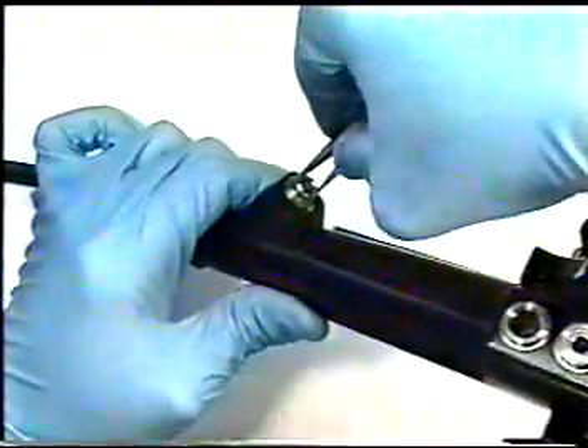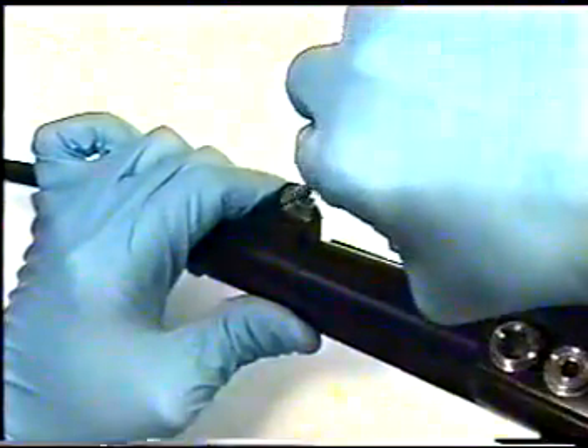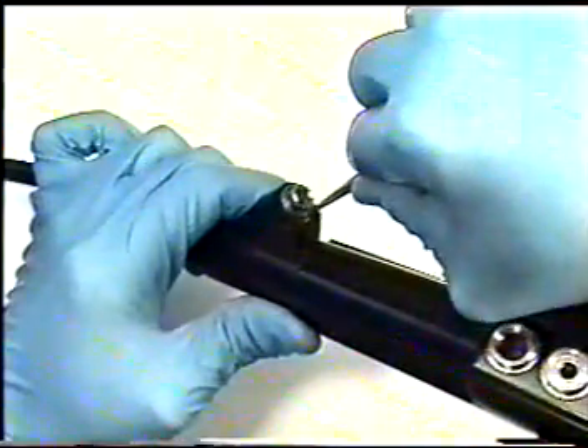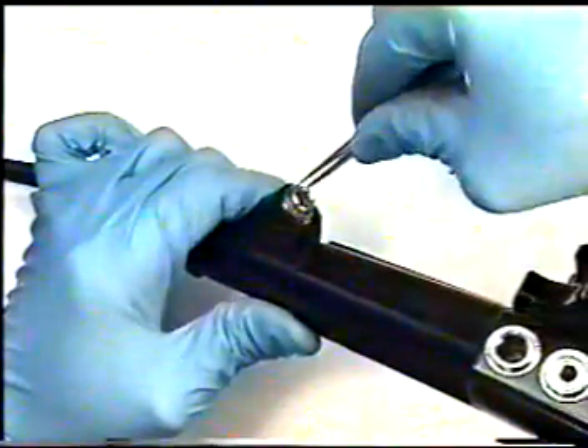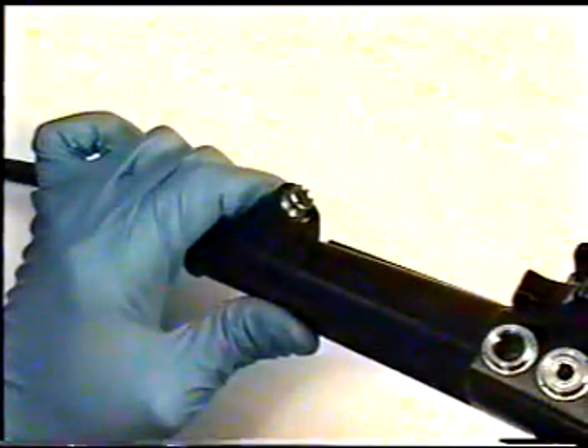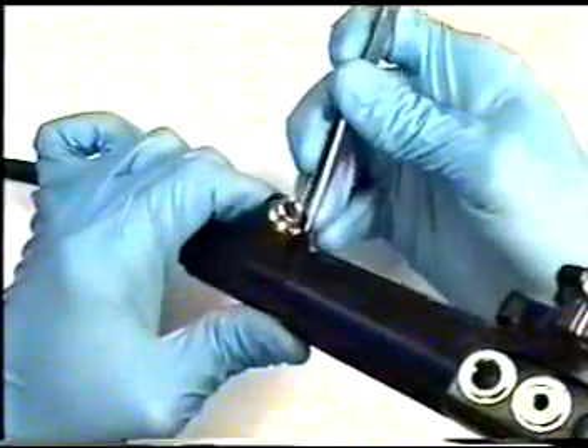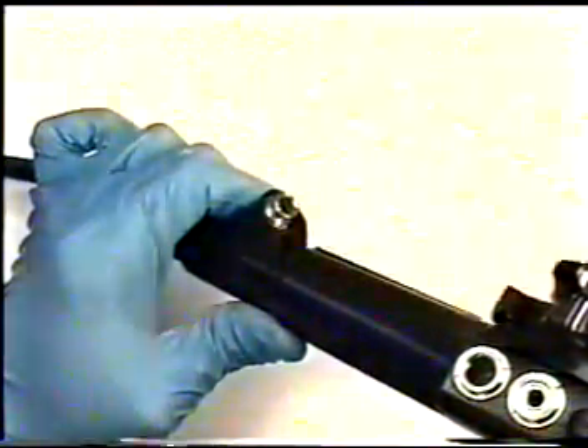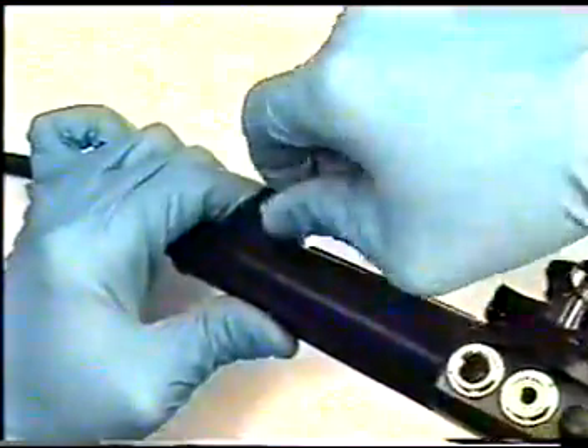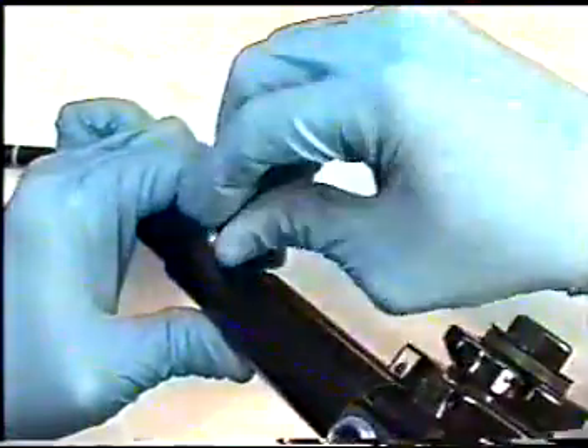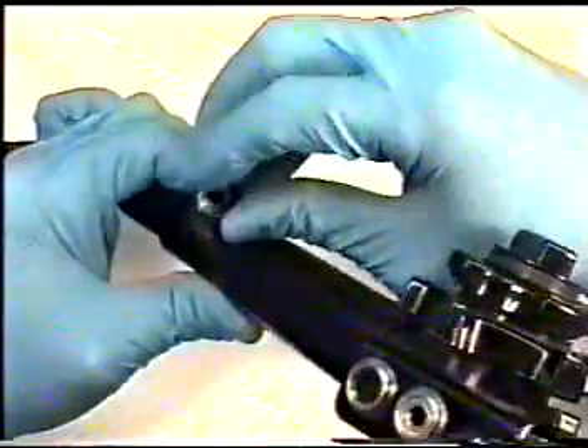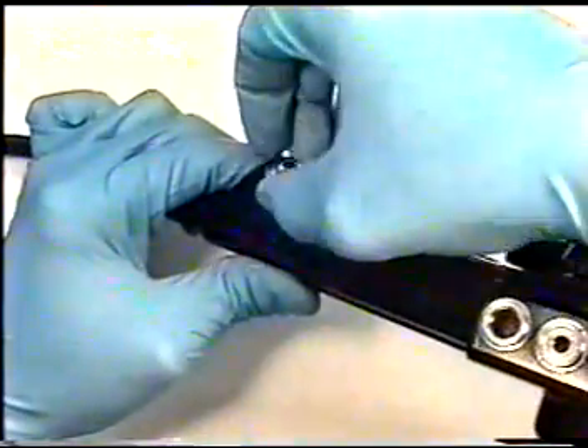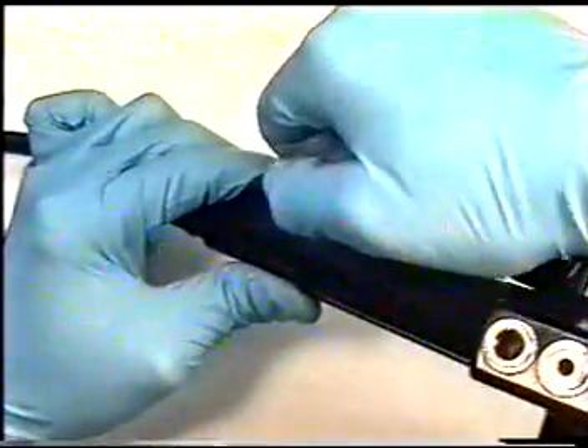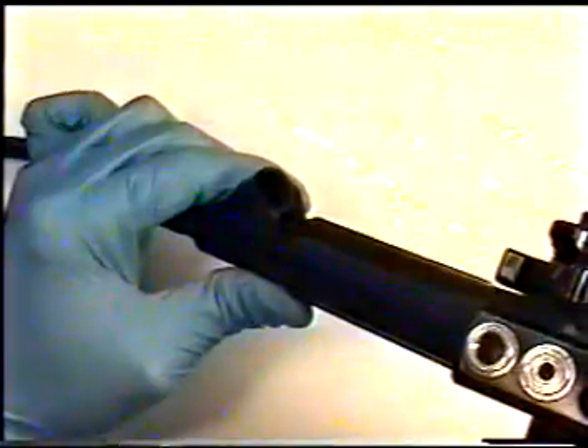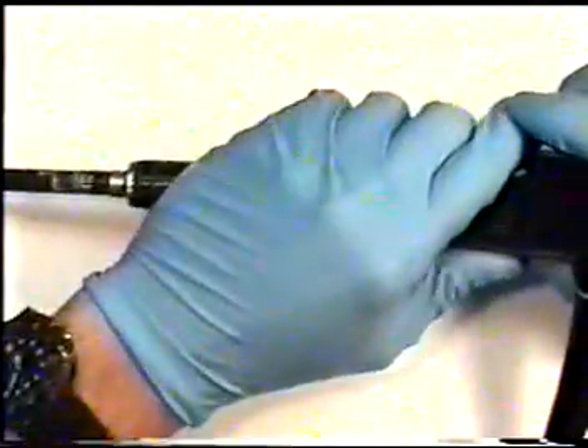Using some heavy-duty tweezers, unscrew your biopsy forceps channel locking ring. Remove the ring and put it in a safe place for reassembly. Remove your biopsy forceps locking key. Unscrew your biopsy forceps valve clockwise or counterclockwise 90 degrees so you are able to pull out the forceps channel valve assembly. Carefully slide down the body cover to the insertion tube.